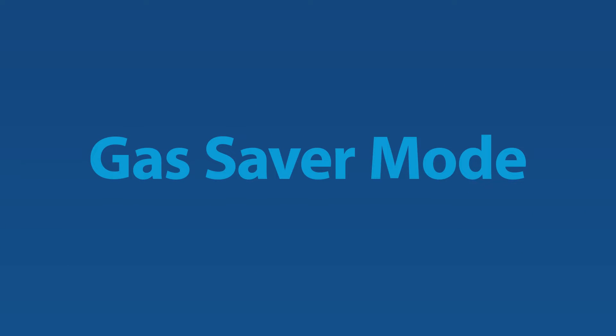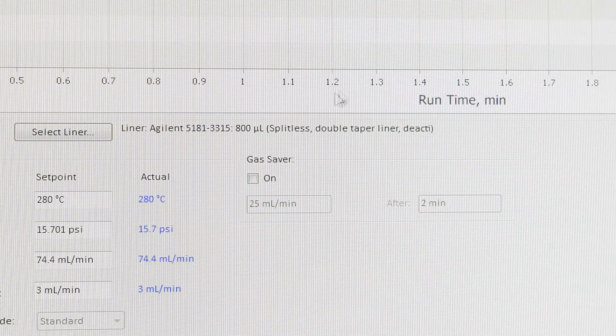Gas Saver Mode. Did you know your GC has a mode to reduce helium usage? It's often called Gas Saver Mode or Carrier Gas Saver. But what does it do?